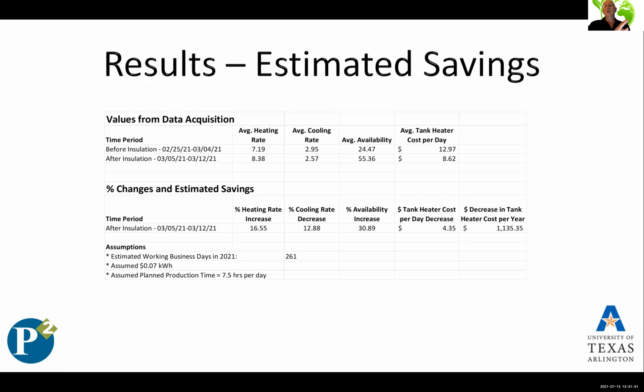We had data collected for 3 weeks, then we put the spheres in and collected 3 more weeks of data. We took days with comparable ambient air, typical outside temperatures, before and after, so we knew the savings were coming from the insulation and not just because a day was hotter or cooler. The tank cost per day before the spheres was about $13 a day, and afterward about $8.50.